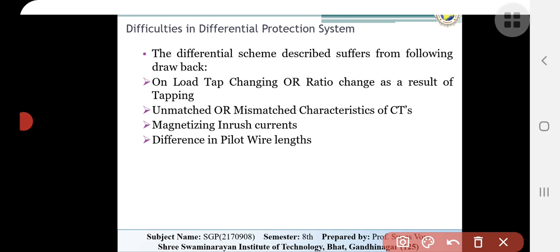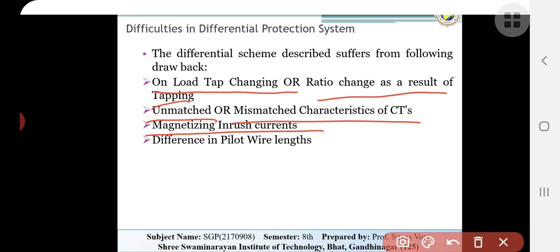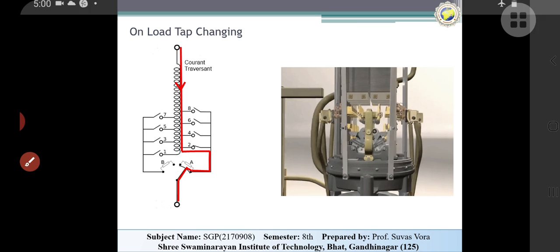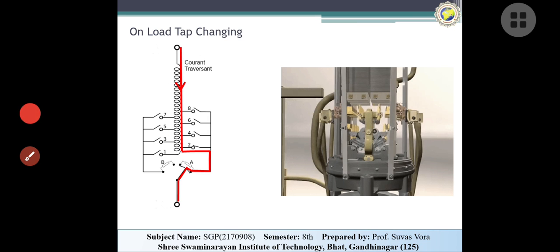So the differential schemes suffer from some drawbacks. The first one is the on load tap changer, then the mismatch characteristic of the CTs, then the magnetizing inrush current, and the difference in pilot wire length. So these four reasons cause difficulty in the differential protection system. The first one, on load tap changing.